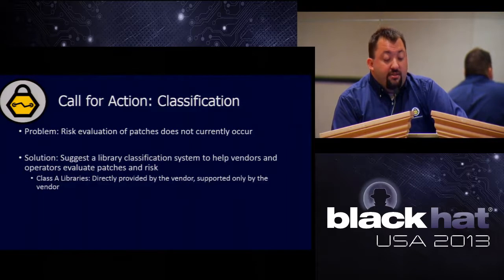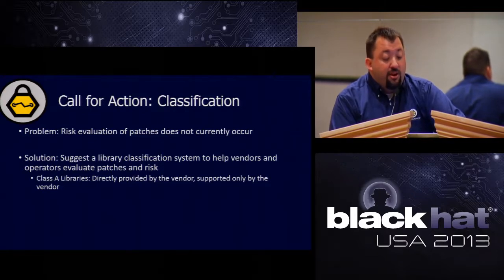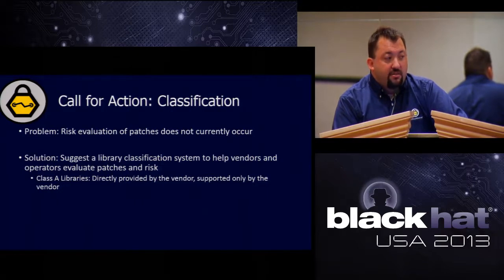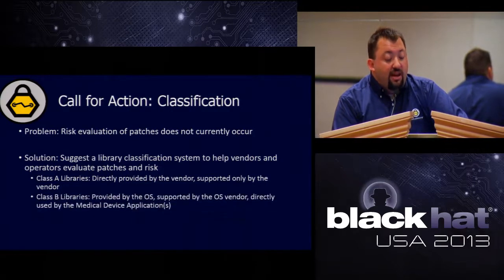My recommendation is to classify the libraries to help vendors and operators evaluate patch risk. A class A library would be one that's directly provided by the vendor and supported only by the vendor. A class B library is provided by the operating system, supported by the operating system, but is directly used by the medical device application.